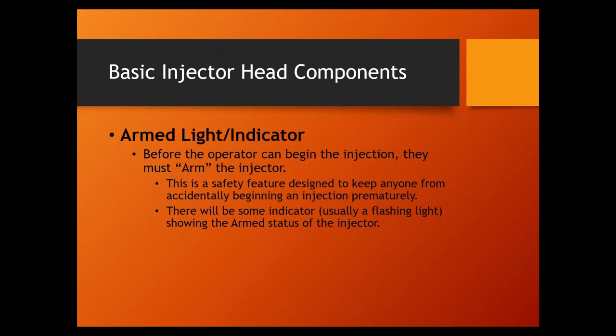Any questions? The PM kits primarily consist of gaskets - there are gaskets around the top, along the sides and bottom that help prevent fluid ingress. It's like a watch rated water resistant versus waterproof. These are fluid-resistant gaskets, and contrast does sometimes get inside the injector head. That's why maintenance on these things is important - it's very important to keep the gaskets fresh and not let them get dry or cracked. Replacing gaskets is part of the annual PM.